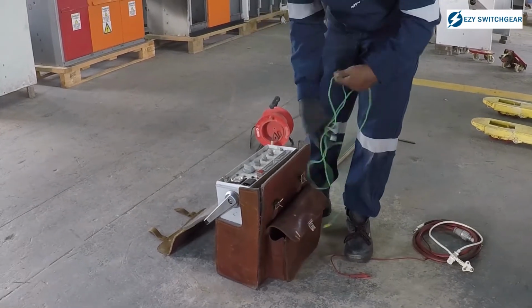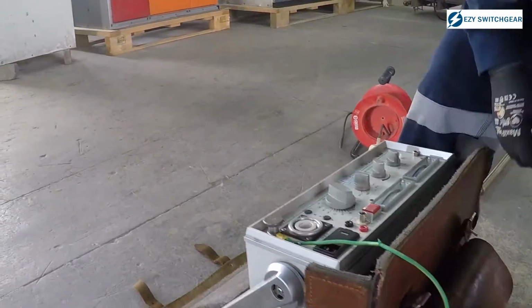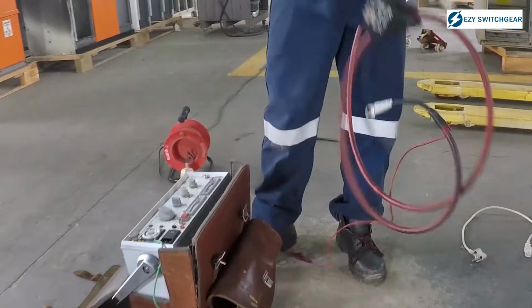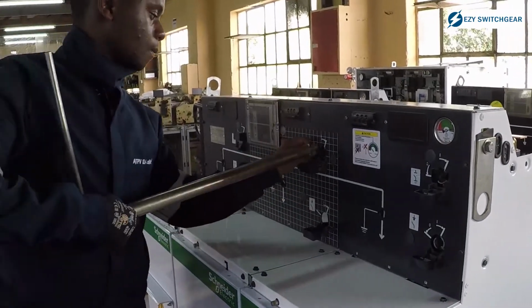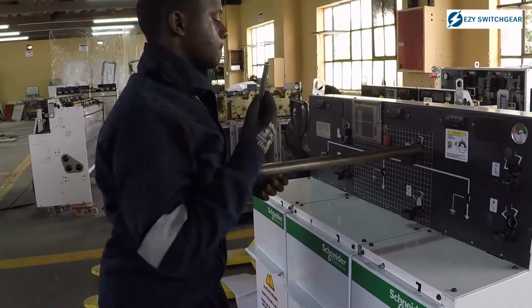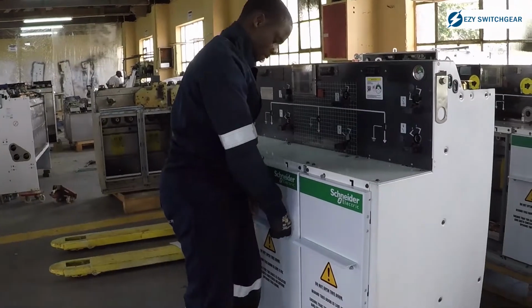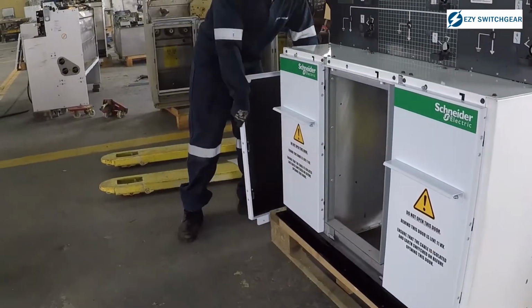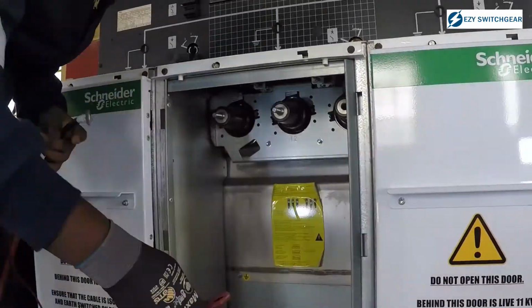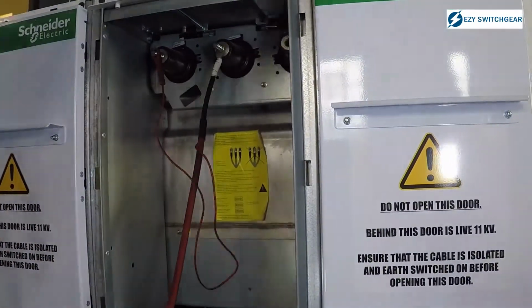This is a test that is twice the nominal operating voltage of the switchgear, which means if you have 11 kV switchgear, you want to put it to 22 kV or even higher. We use 25 kV because that's the voltage that we feel is safe, and therefore each switchgear that passes through that high voltage test will surely work on the network.